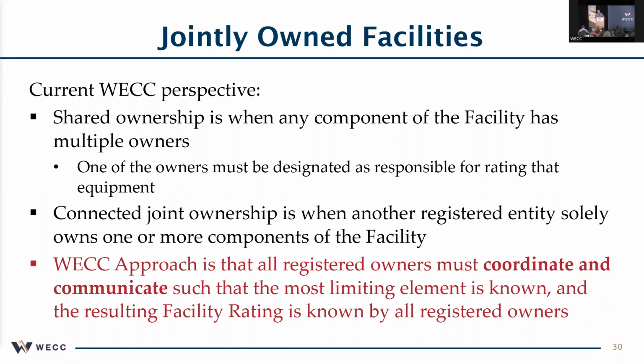For connected joint ownership, when another registered entity solely owns one or more components of the facility that are directly connected to each other, WECC's approach is that all registered owners must coordinate and communicate such that the most limiting element is known, and the resulting facility rating is known by all registered owners and agreed that they're operating to the same facility limit. That is what gives us a certain amount of comfort that the system can be operated reliably, that the facility rating can be used in an open access tariff. It can be used to make an SOL. It can be used to put in a planning standard, and it will work.